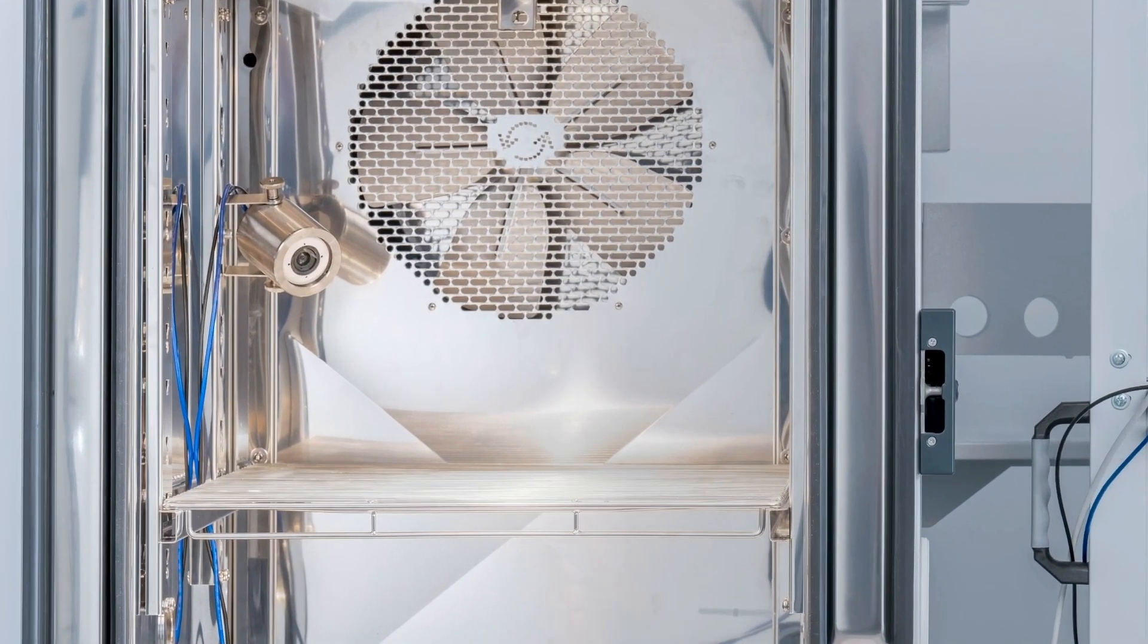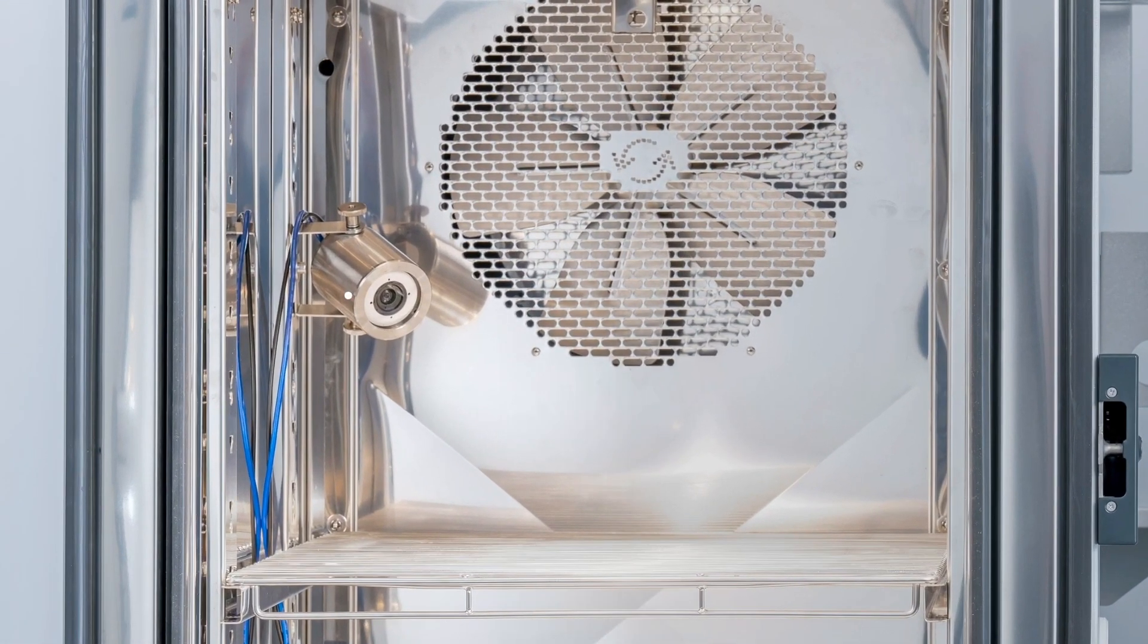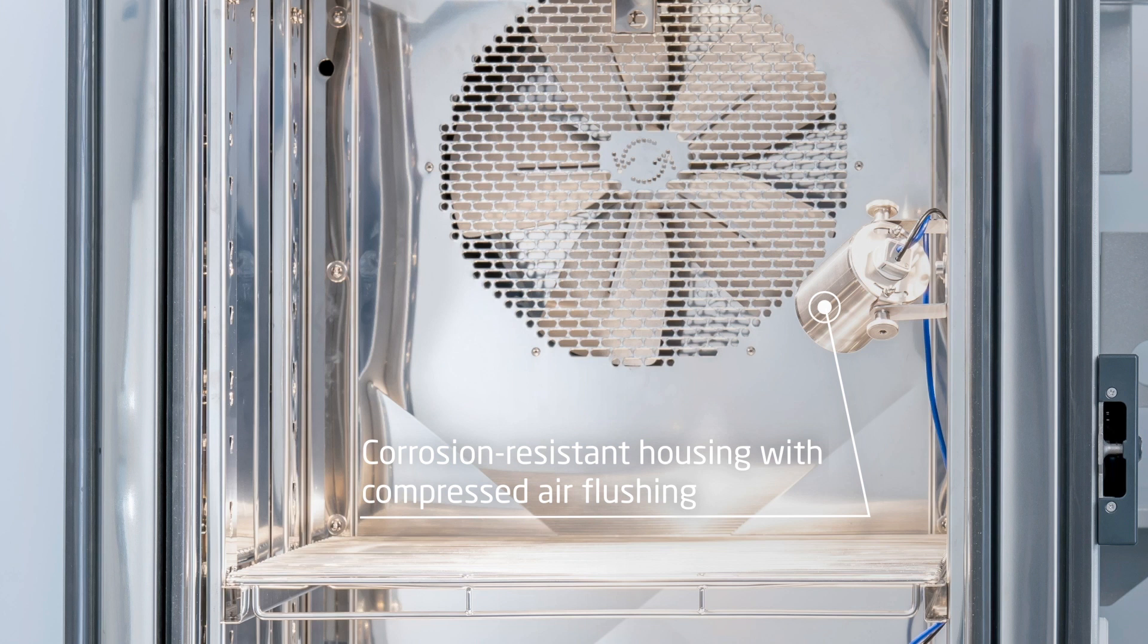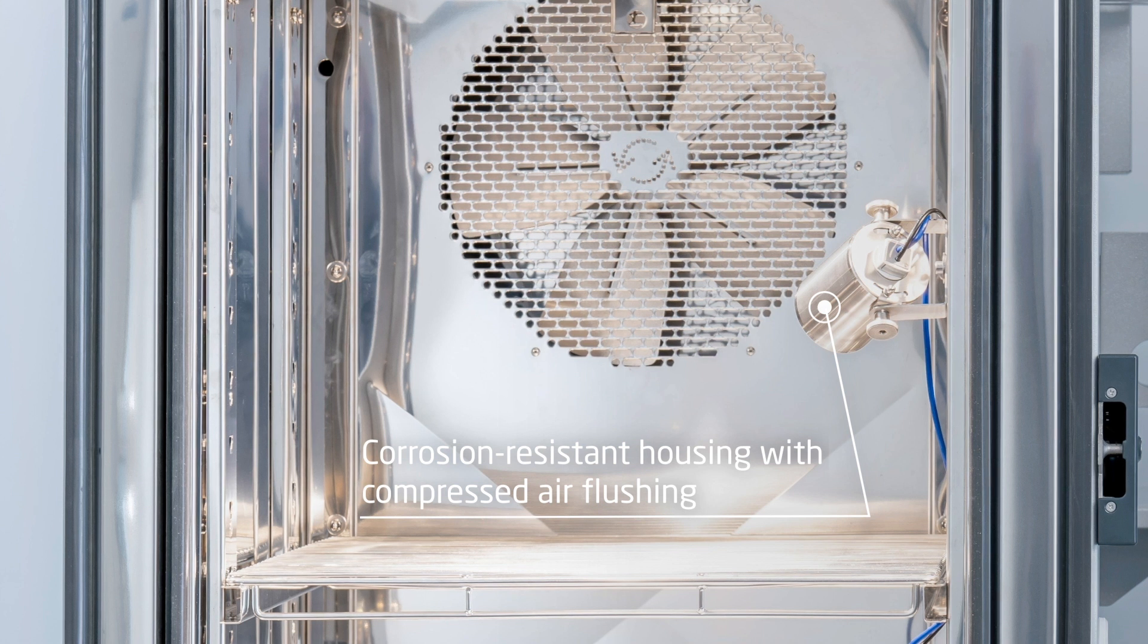The camera module with lens is located in a corrosion-resistant housing and can be flexibly mounted in the test chamber. To prevent the lens from condensing in climatic conditions, the housing is flushed with compressed air.